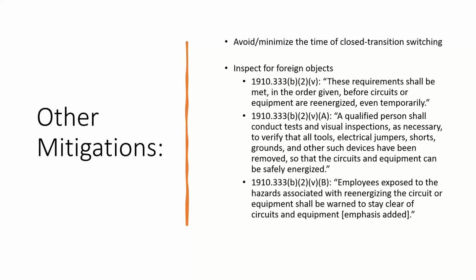And again, on inspecting for foreign objects, there are some requirements that OSHA has, to make sure that you've inspected for all that before you re-energize. A qualified person shall conduct tests and visual inspections as necessary to verify all tools, electrical jumpers, shorts, grounds, and other such devices have been removed. So all those words, when it says qualified person, what makes somebody qualified? That could be a point of argument, probably. Employees exposed to the hazards associated with re-energizing a circuit or equipment shall be warned to stay clear of the circuits and equipment. So obviously, you want to be as far away from them as you can be whenever you re-energize.